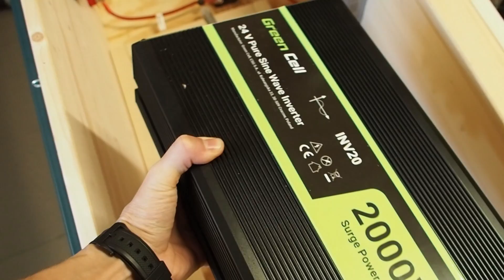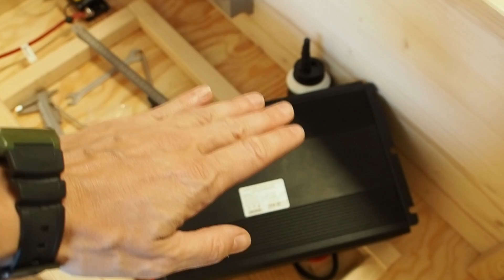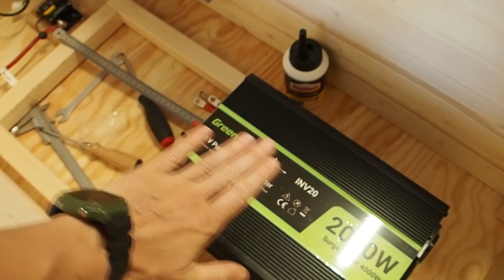If you take a look at the label here on the back side, you can see that you have to install it upwards and not sideways. You cannot install it sideways to the wall, because with the vibrations going on, all of the electric parts could bend down when they get hot. This is why you can only install the inverter like this.